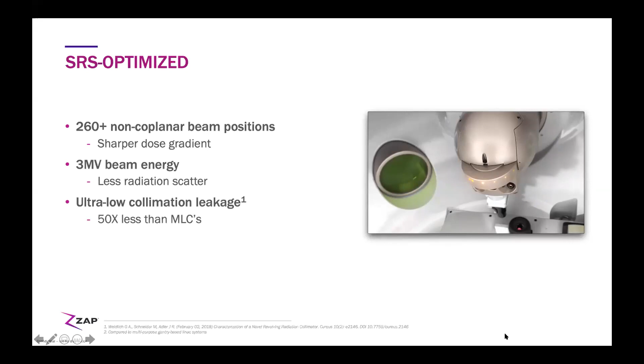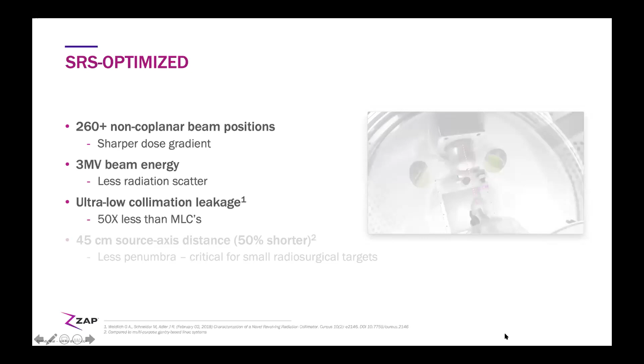So really all you're dealing with is the beam that comes out of the central axis of the collimator, as we'll show you in a little more detail. And then lastly, by using a 45 centimeter or 450 millimeter SAD, we have less penumbra. So we have multiple different attributes, the way we fire radiation out of this device, that gives us the steepest possible dose gradient. And I likened it to the sharper knife. So how is it sharper?